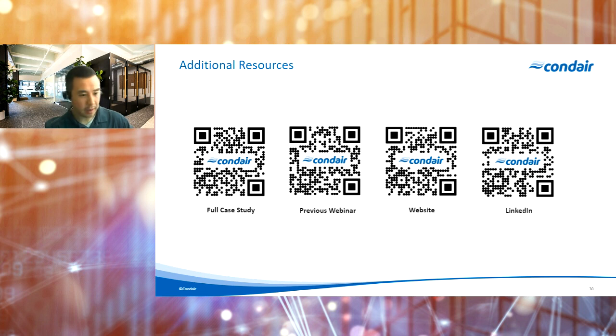So we've got probably time for one more quick question here. I see one. Can ultrasonic systems be used in a residential setting? They can. The only thing that you would want to keep in mind there is just that absorption distance. Generally with the smaller capacities, if you're just looking for humidification, the plume is going to be relatively small. But if you're on that higher end of the capacity outputs, in the 40 pound an hour range, you may have absorption distances of 10 to 15 feet. So in a residential application, it's going to be a little bit trickier to do.